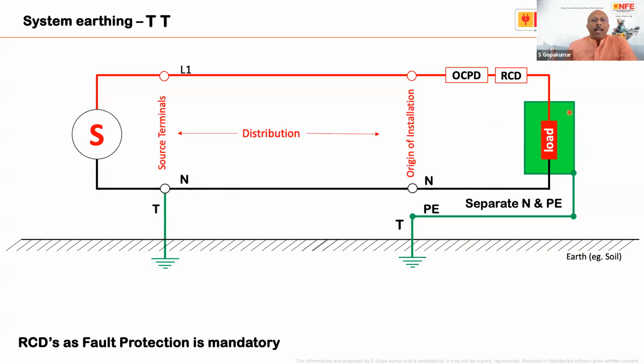The equipment, actually in one installation, that means in one apartment building having maybe 100 apartments, all the exposed and extraneous conductive parts of that particular building must be interconnected to a common bus bar, and the common bus bar can be connected to one earth electrode. That is the correct TT. Now, both these earth electrodes are electrically isolated. They have to be placed away so that the influence potential rises are not influenced. So we call it an electrically independent earth electrode.